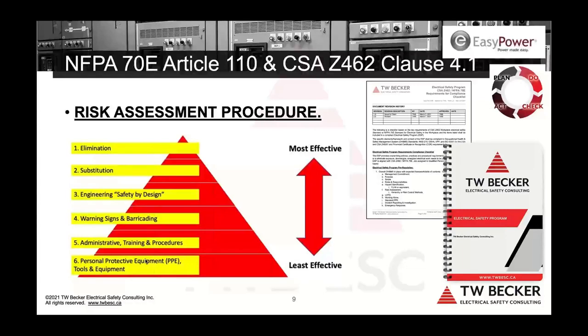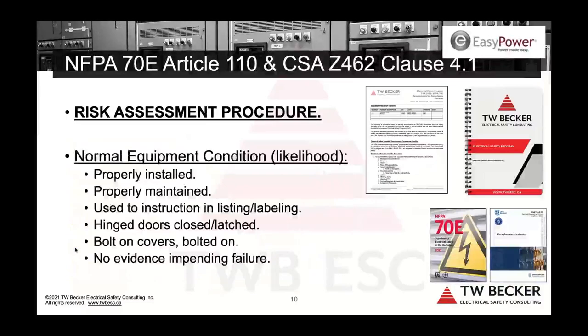And then the studies, arc flash hazard incident analysis studies and equipment labels, that provides the arc flash hazard information for the worker so that when they're implementing this energized electrical job workflow, they get the label. The label is the best method to get the arc flash and shock hazard information in front of the worker on the electrical equipment before they work on it. And then they use that to document their job safety plan. All right, so some focus on normal equipment condition related to risk. This is all part of the risk assessment procedure.